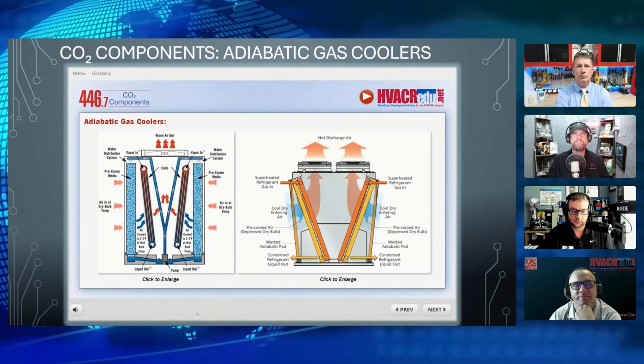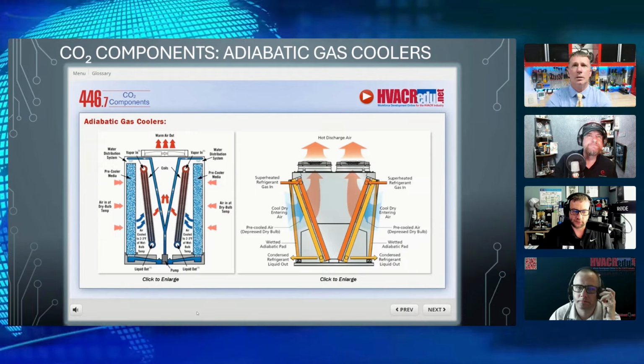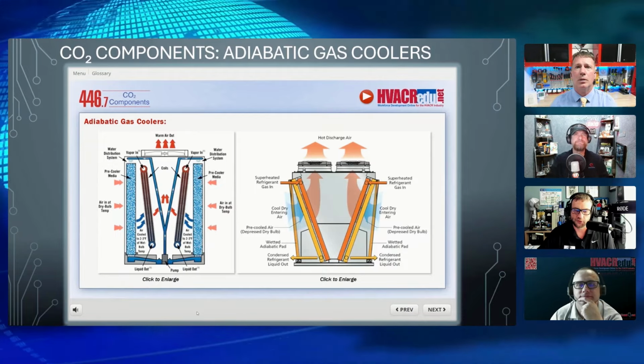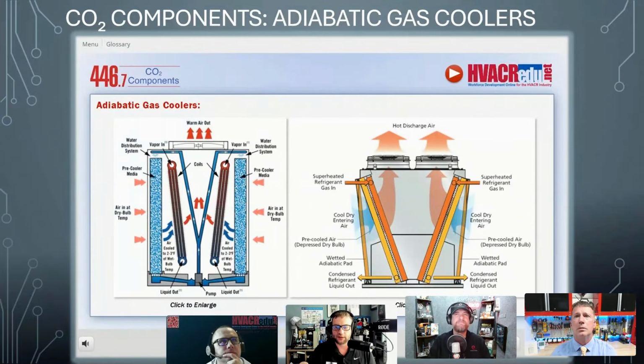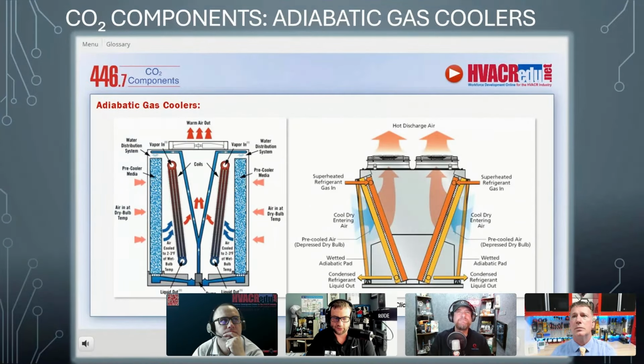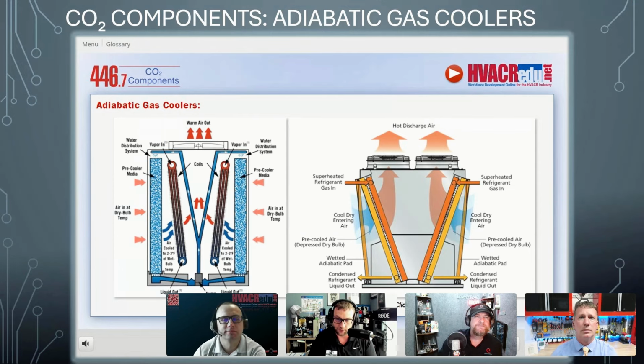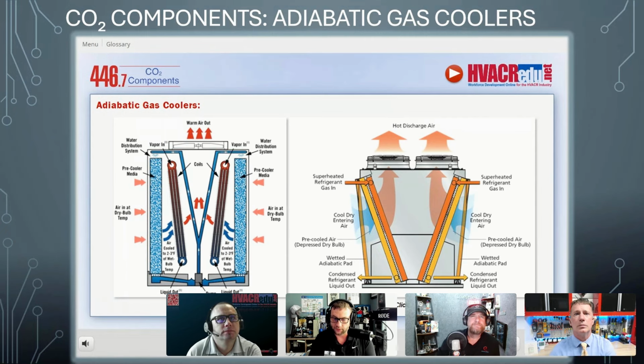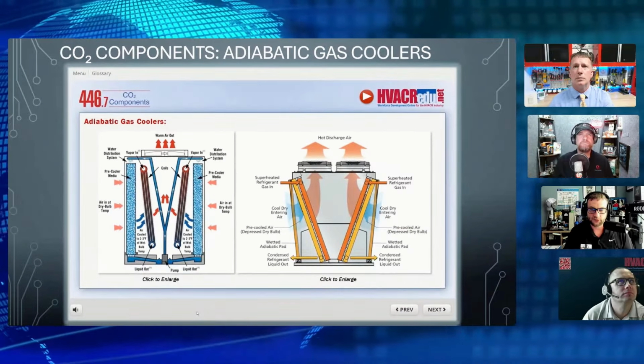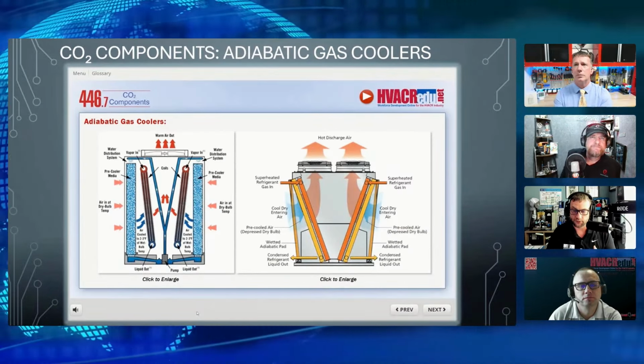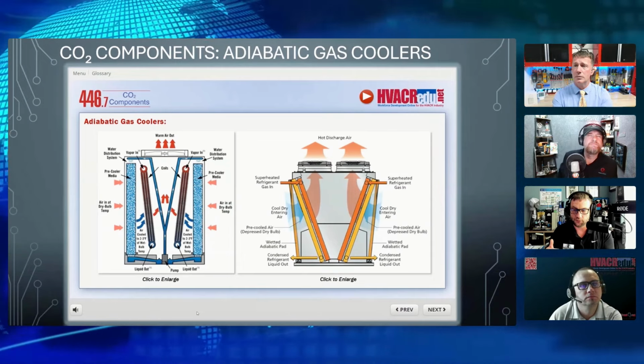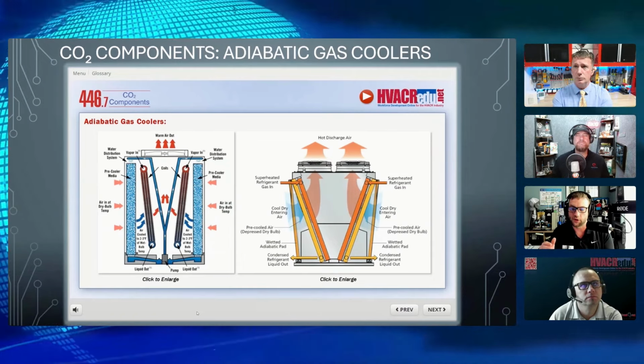Go ahead, next slide. This is just a little bit more of a diagram to break down what's really happening here. You have a water distribution system, so it's different than a conventional evaporative condenser. In an evaporative condenser, we typically put the water over the actual tubes, which requires water treatment. This doesn't require water treatment. It has its own self-sustaining pump, pumping that water up into the feeders, dripping over those pads. Some are more advanced than others. Some just circulate constantly. Some actually use humidity and dew point temperatures to see how much water they should mitigate through there in order to utilize the most amount of water through the passes.